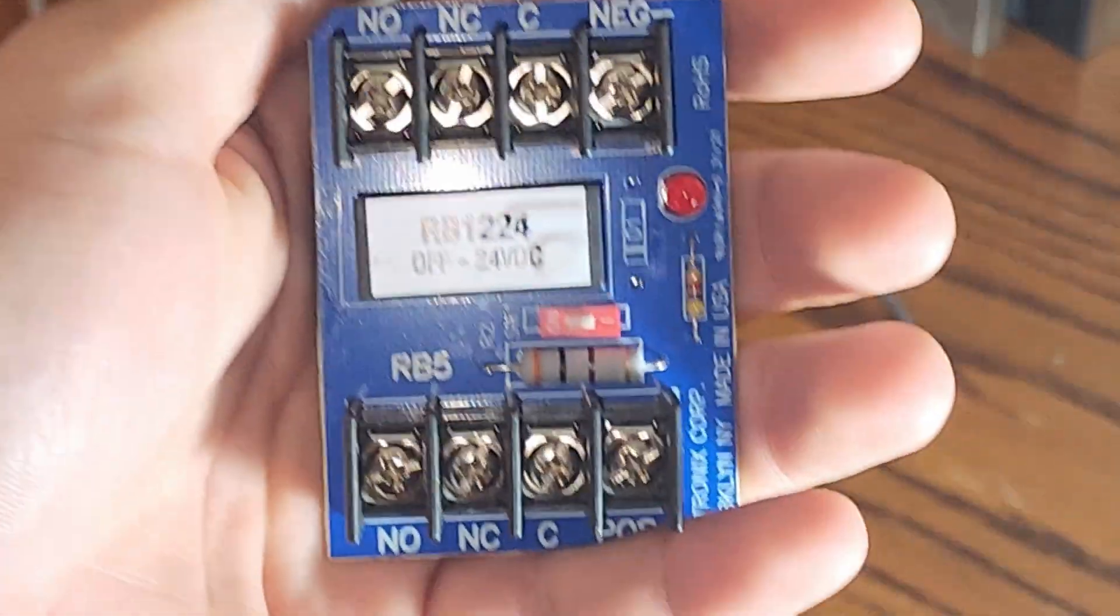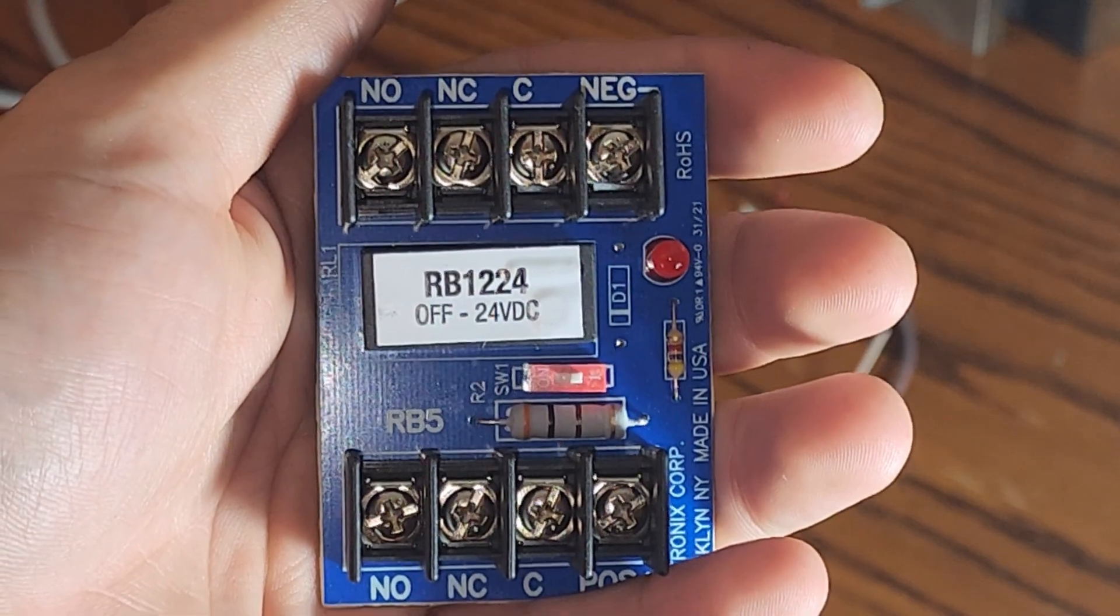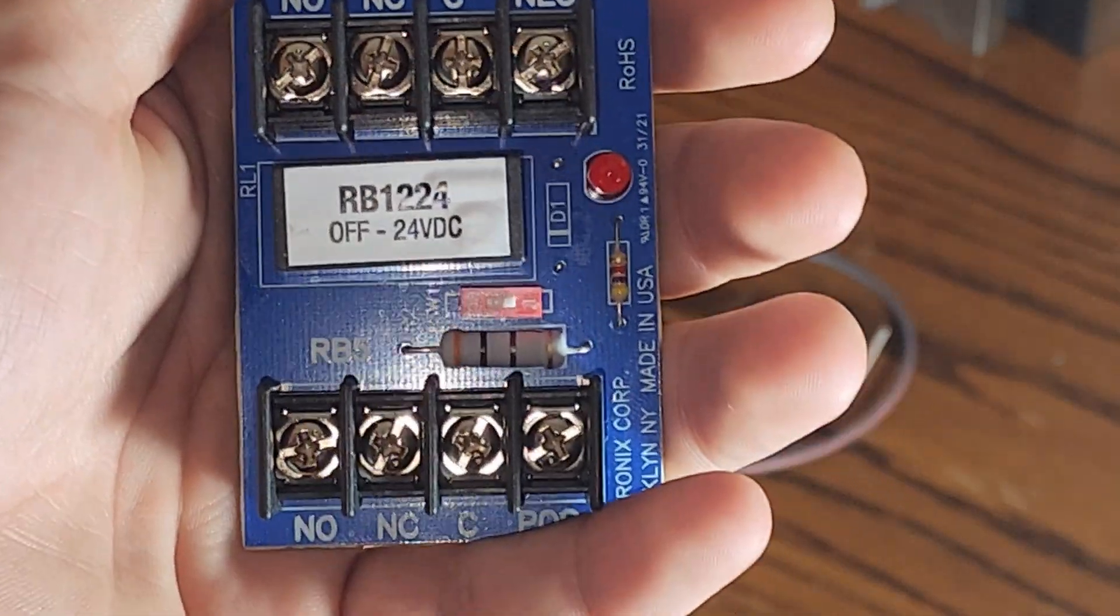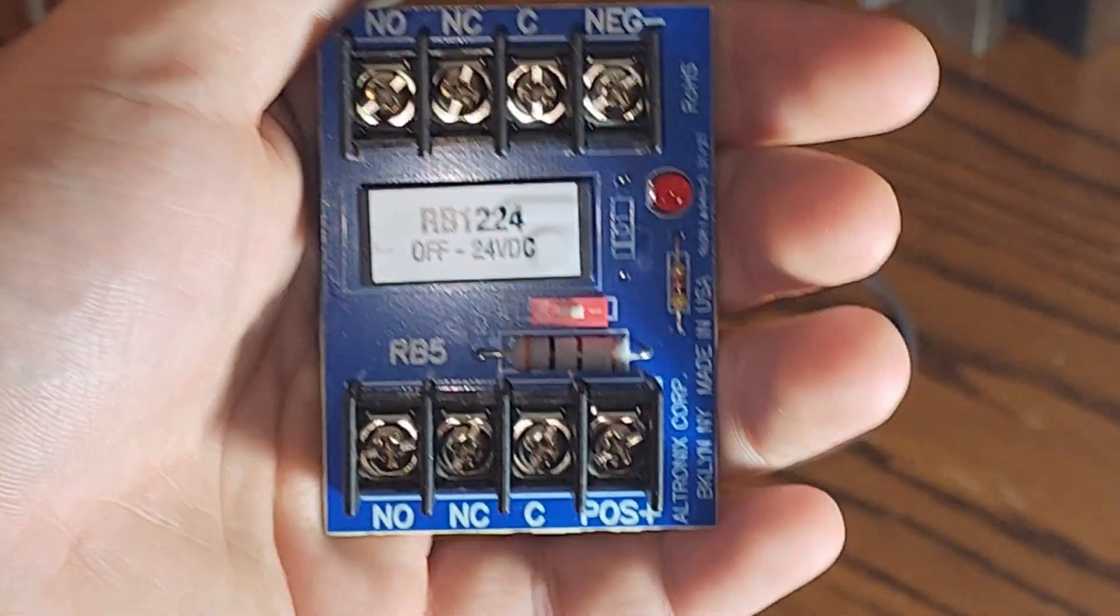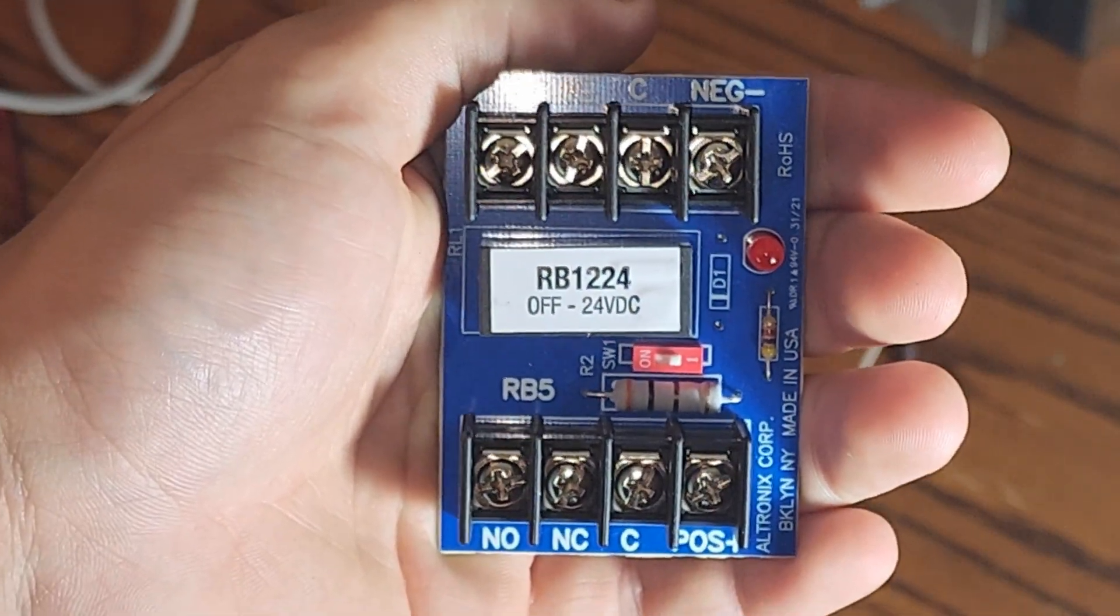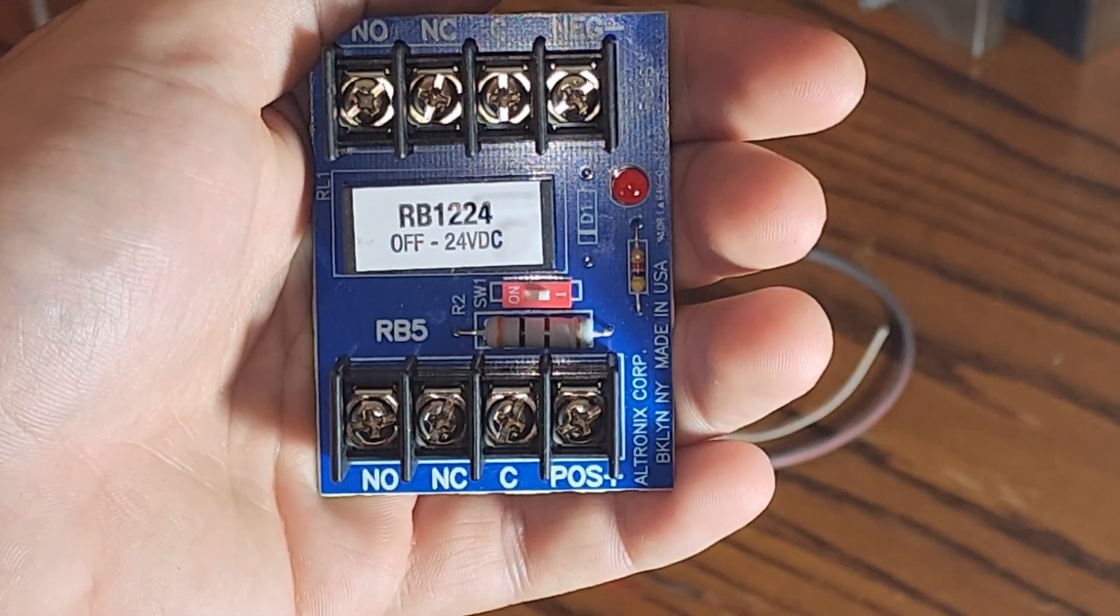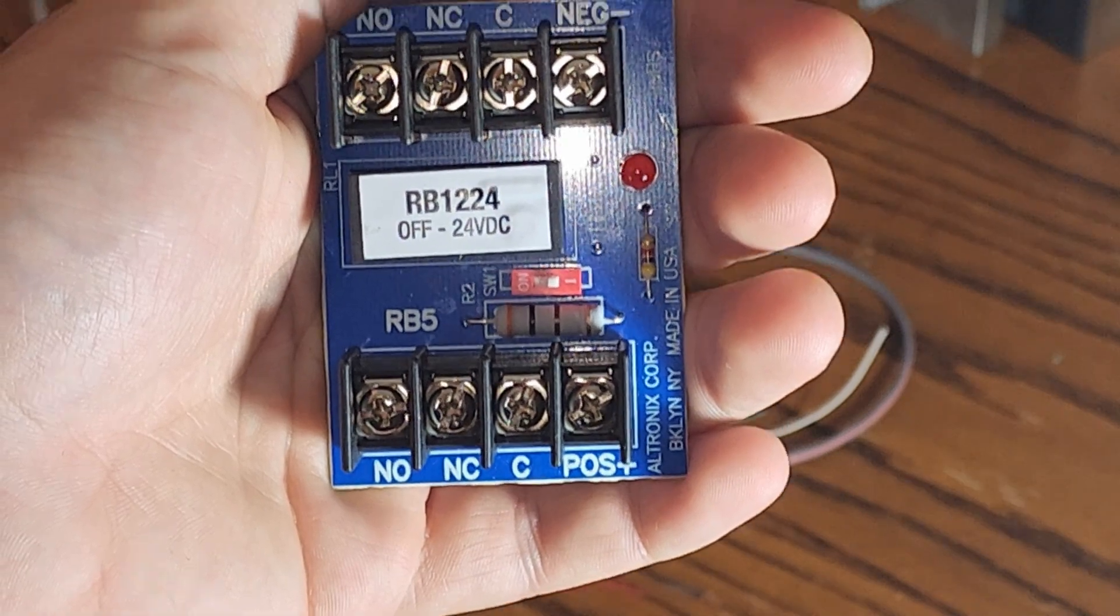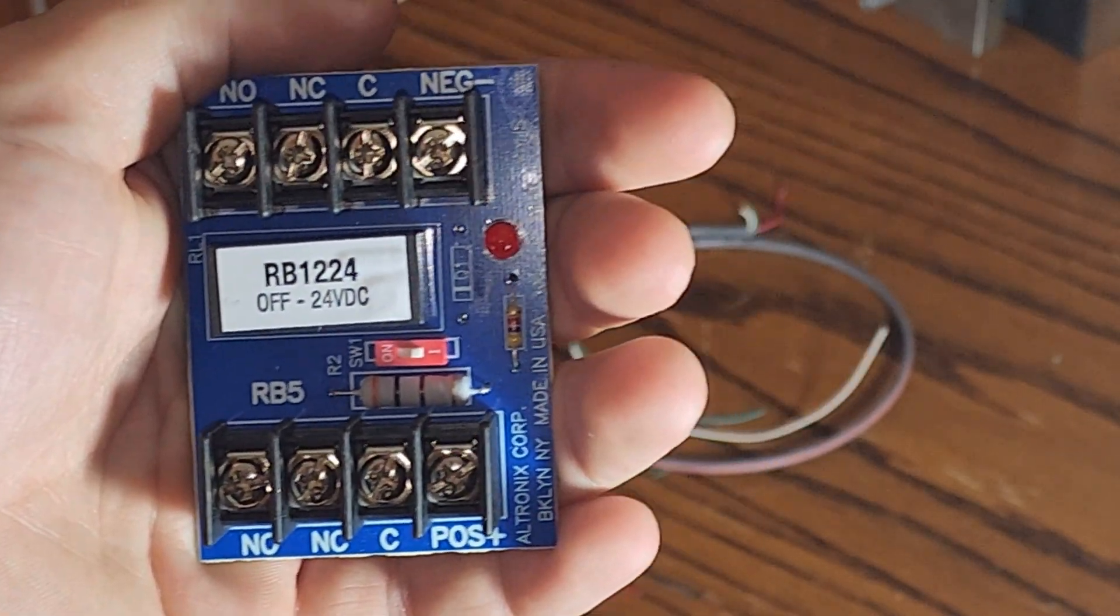What would be the use case for one of these relays? We talked about giving it a trip, but how do you give it a trip? Well, generally, that's another relay, and the reason for that is because the relays that come in our devices are often very small and internal. They can't handle that much current, and if you try to run too much current through them, it either just won't work, or you will burn the relays out.